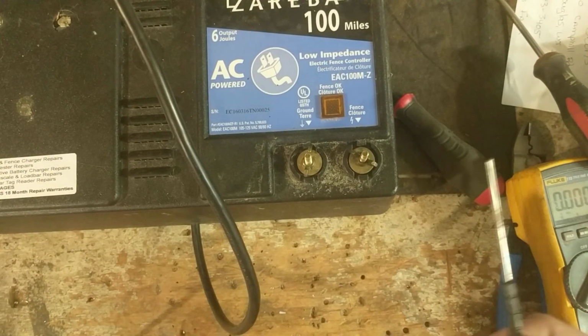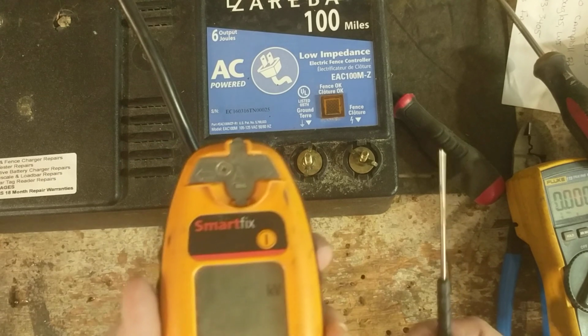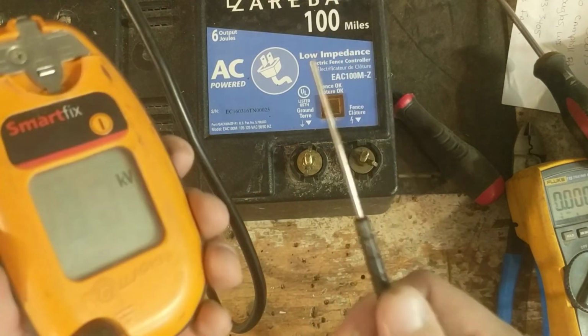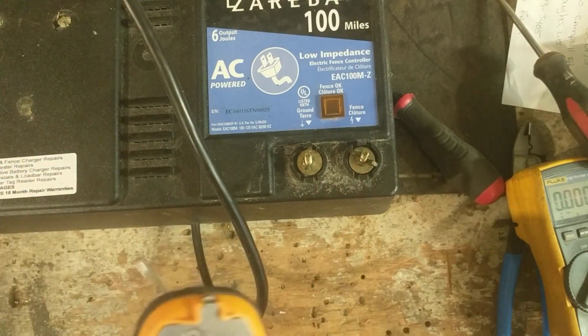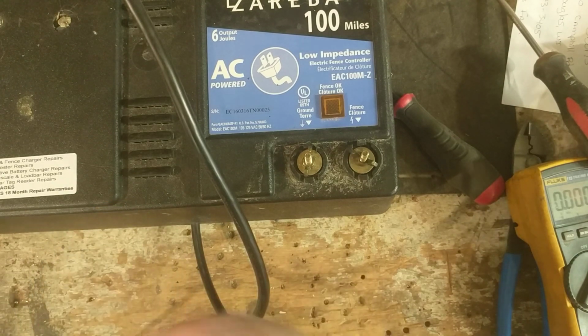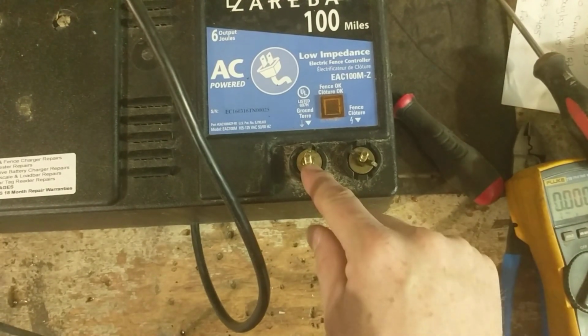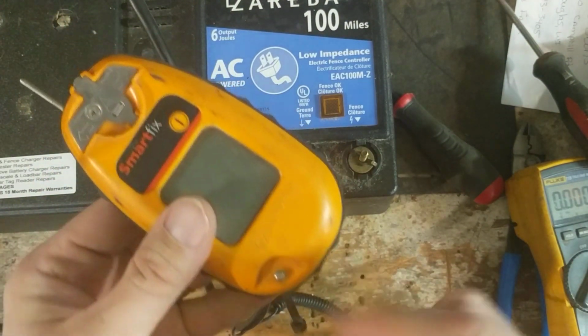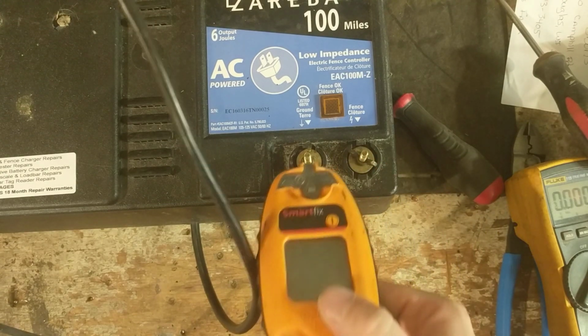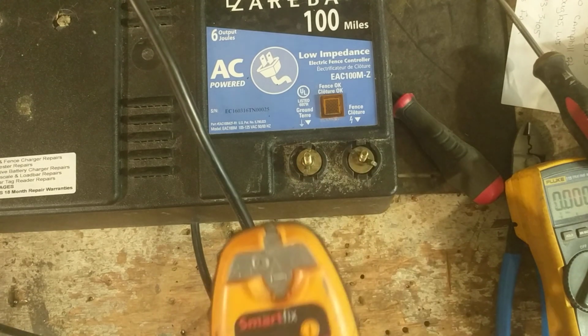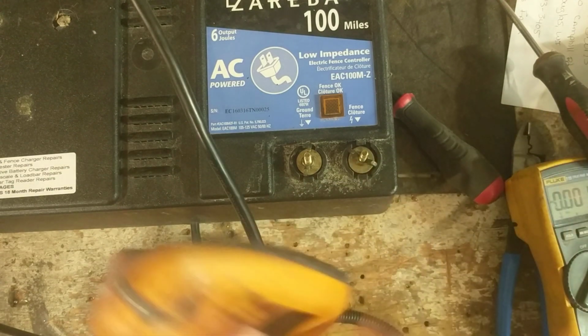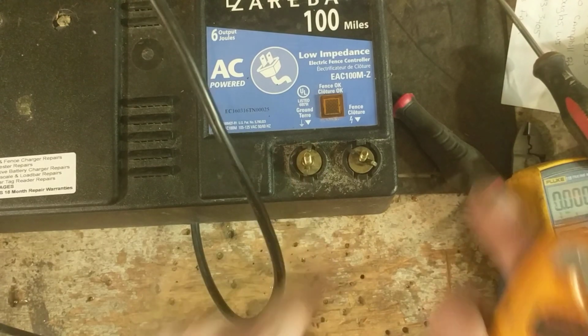To test the unit on its own, you have to have the ground probe on this unit touching the ground side. Or if you don't have the ground probe, you can get a little piece of wire with an alligator clip and clip it onto the ground terminal peg here. If you touch just the hot side, you'll get a partial reading, because you have to go between ground and fence at the same time with this tester. Out on the fence, your body's acting as the ground, so you're basically touching it when your hand is on the back of the unit while holding it.